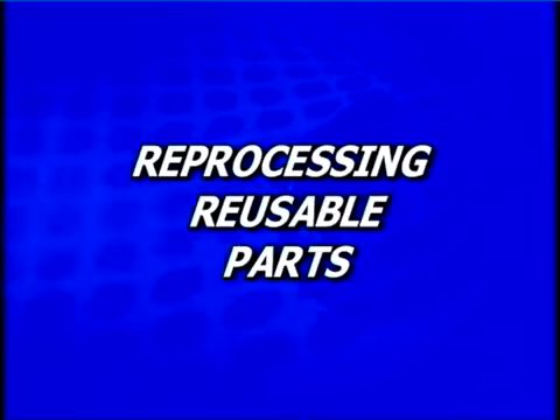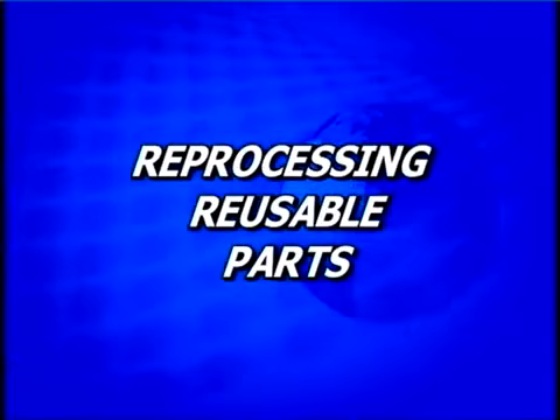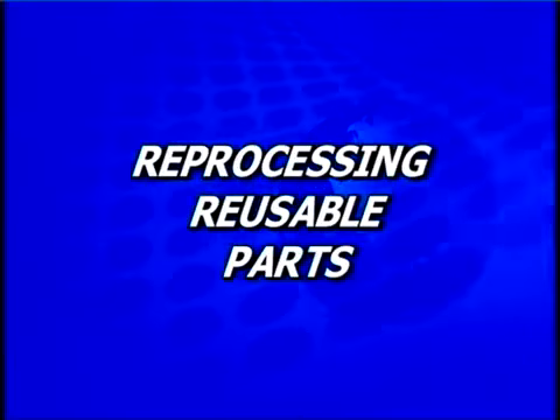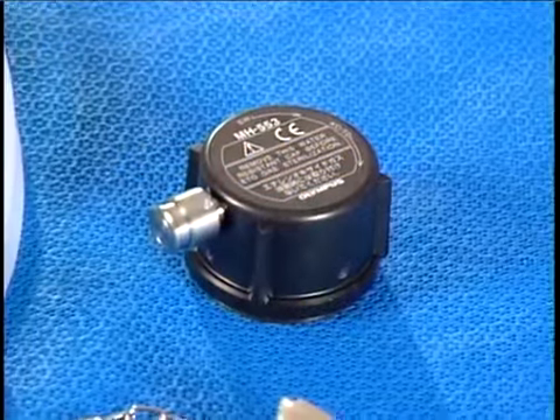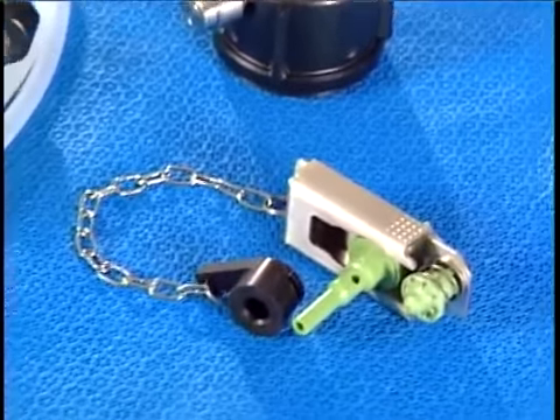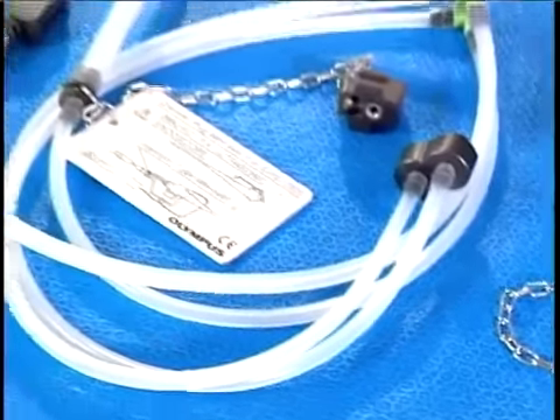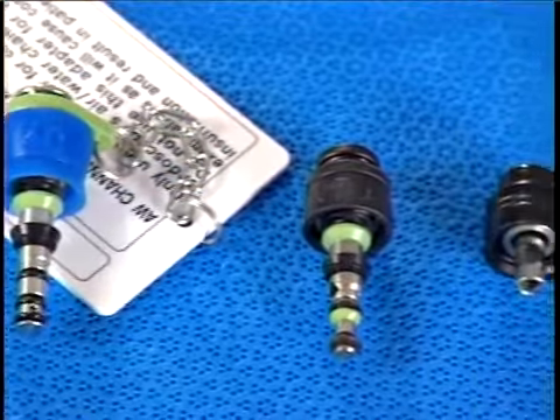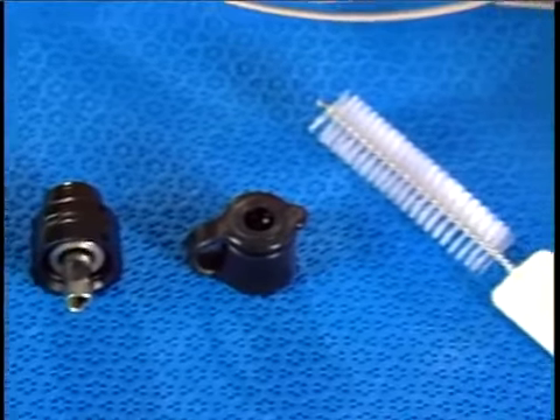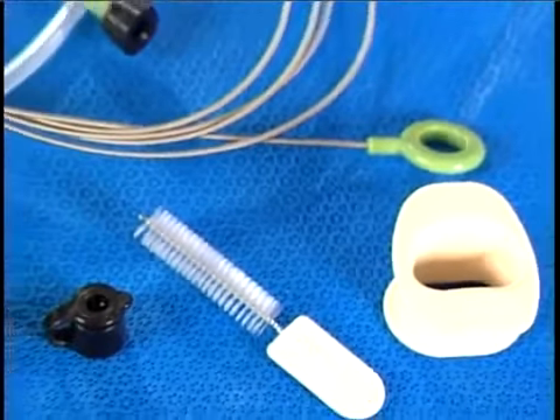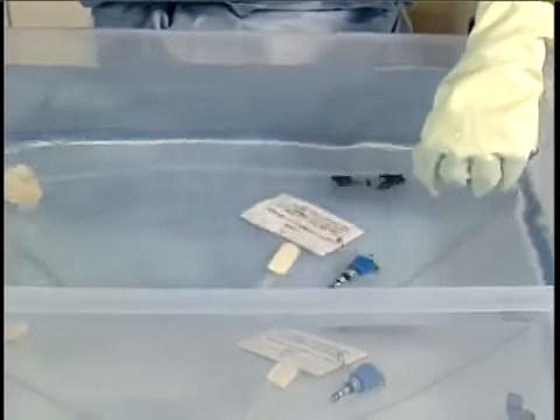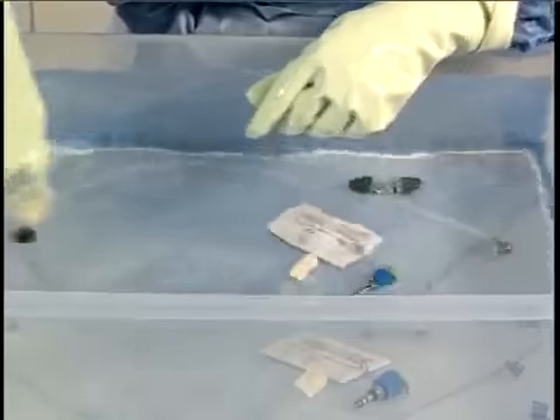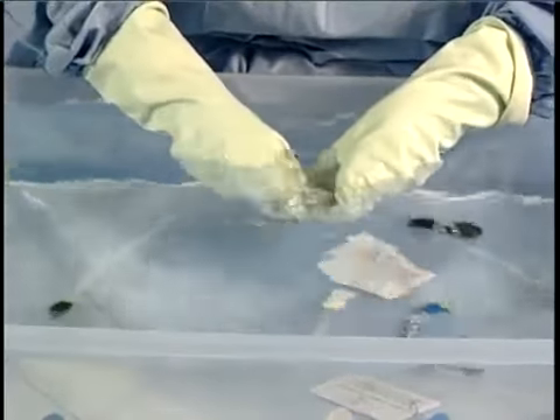Now that the endoscope has been reprocessed and stored, a few words regarding the reprocessing of ancillary equipment. Note that the water-resistant cap, channel plug, and injection tube have been reprocessed along with the endoscope. This leaves the valves, suction cleaning adapter, reusable cleaning brushes, and mouthpiece to be reprocessed separately. Using a clean, soft brush, sponge, or lint-free cloth, meticulously clean the outer surfaces of all parts in the detergent solution. Clean the bristle sections of the cleaning brushes thoroughly while immersed.